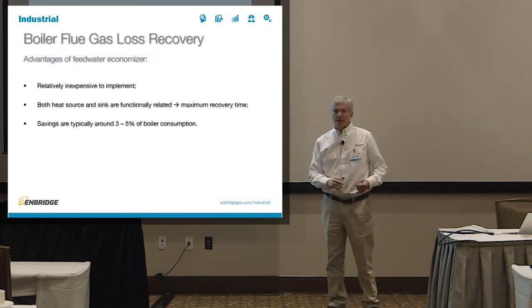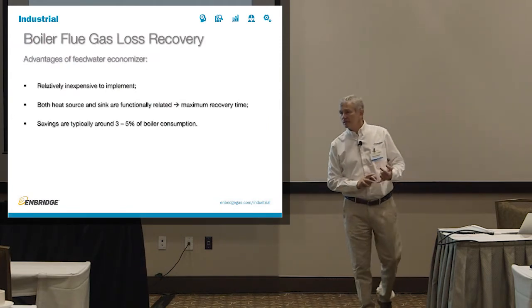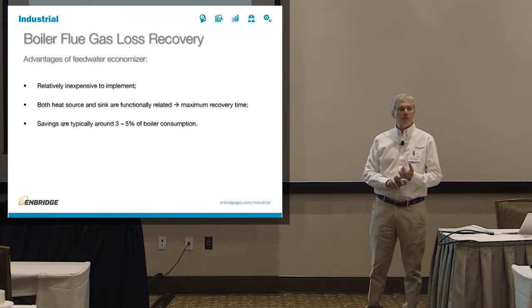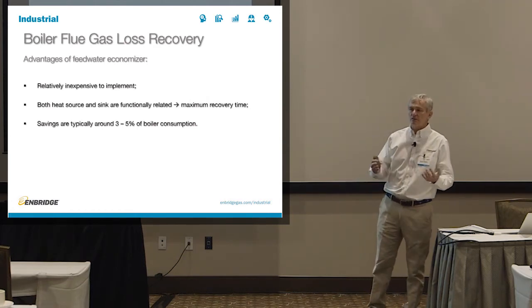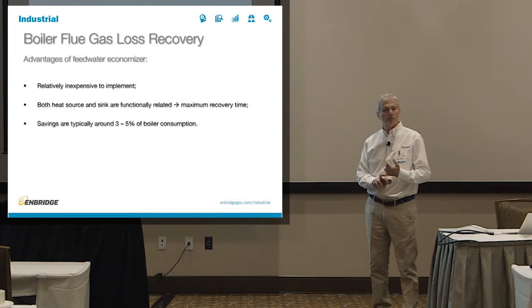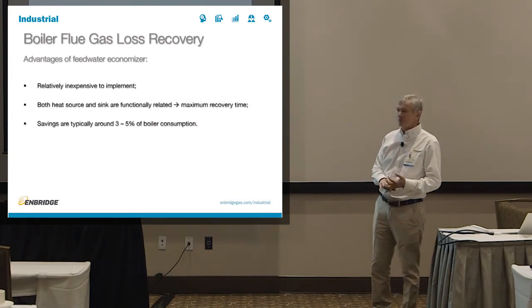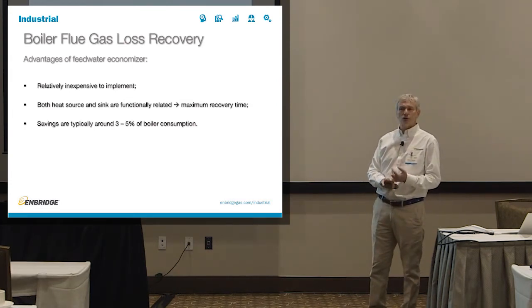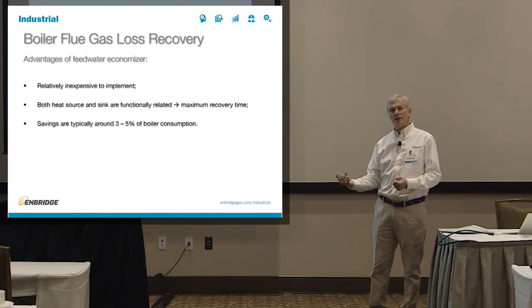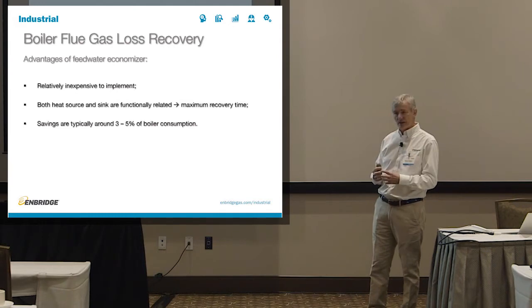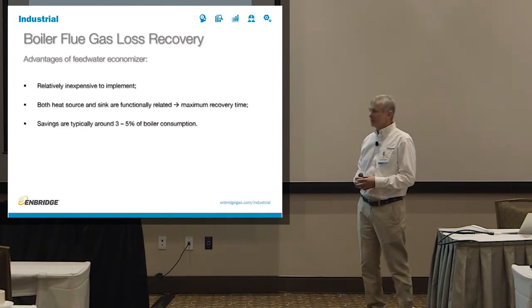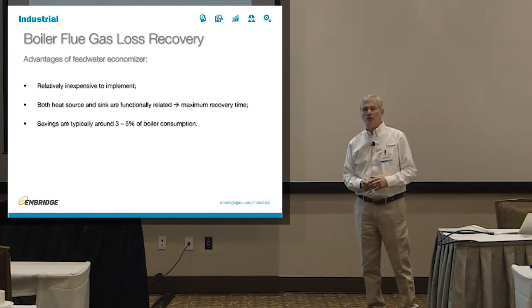So to recap, the advantage of the feed water economizer is that they're relatively inexpensive to implement. You've seen the $20,000 to $30,000 is typical price range. Both heat source and sink are functionally related, so you don't have to worry about when you have a heat sink, when you have a heat source, and match them up. They're automatically matched up. And the savings are about 3 to 5% of the boiler consumption.